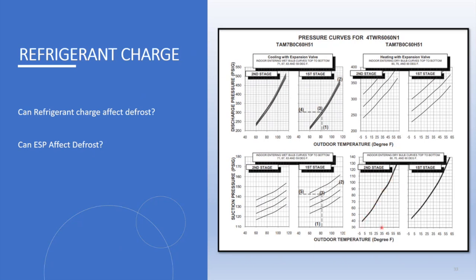like one thick one. On your low side, which you would be measuring just below the reversing valve inside the indoor unit, there's a port there that you would be checking from, and you should see about 85 PSI. So if you have the correct PSIs per this chart, you probably have the right amount of refrigerant in there, and I'd probably start looking at other things.